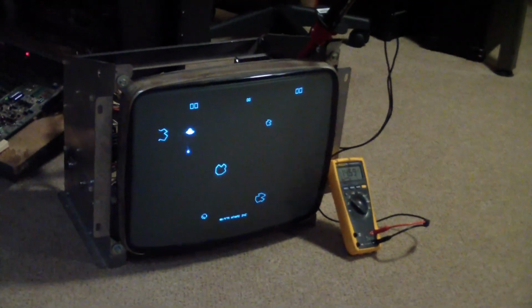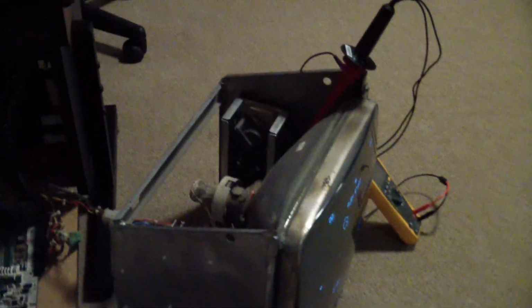It works, it works. And to do the corona test, I'm going to turn off even more lights. And yes, I'm pointing straight at the high voltage cage. Nothing's arcing, so my insulation is good.